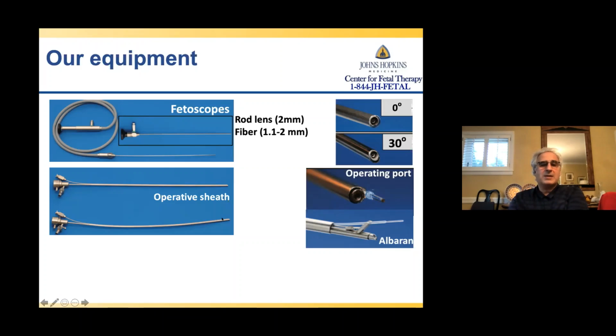The other thing is these instruments are very, very delicate. And so most of them come with standard containers, or specialized containers are very, very expensive or not available everywhere, so that there is a pretty high rate of destruction in the sterilization process. And because they're very specialized instruments, many times people may not be aware of what this looks like normally, right?